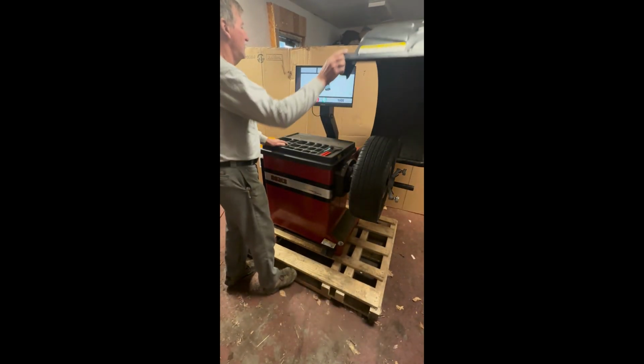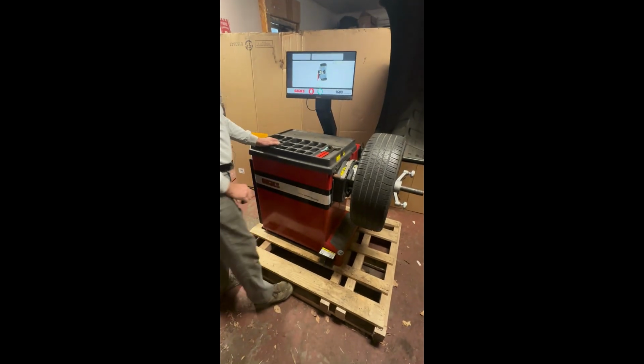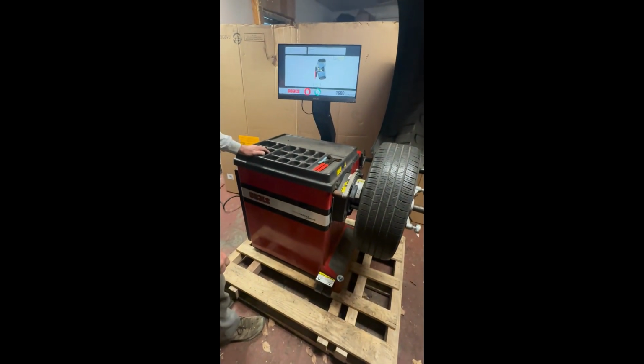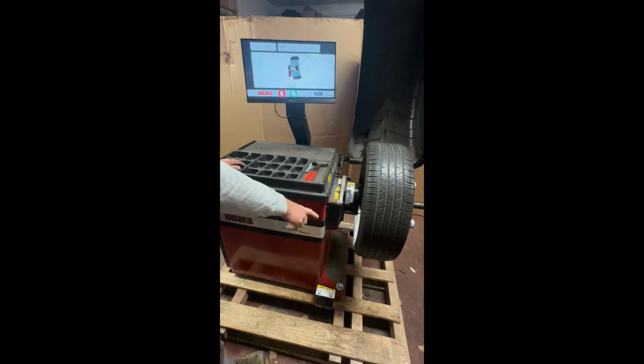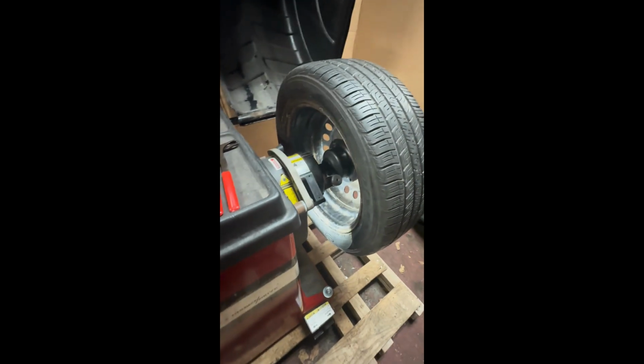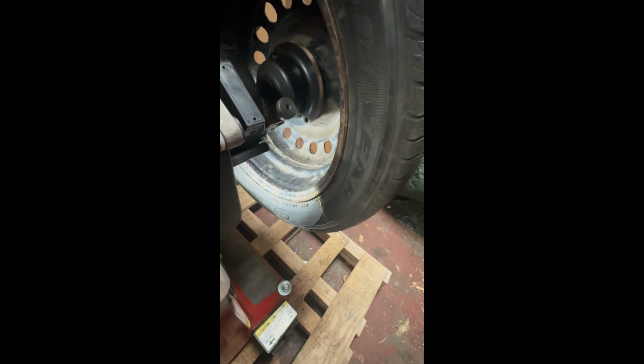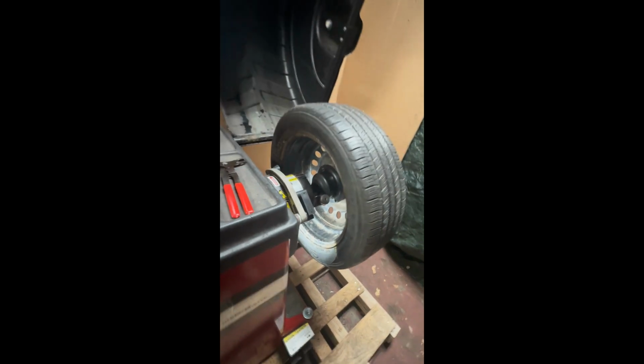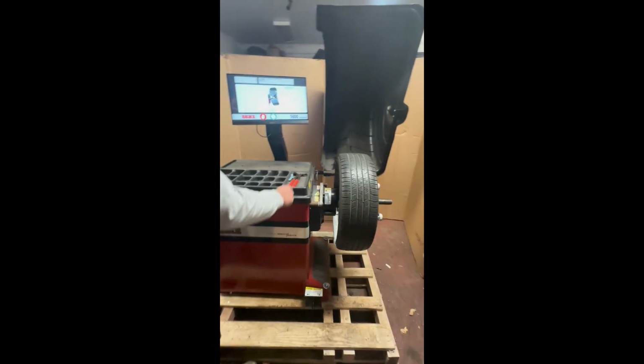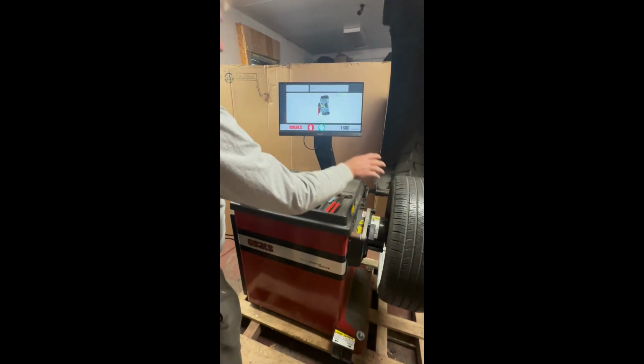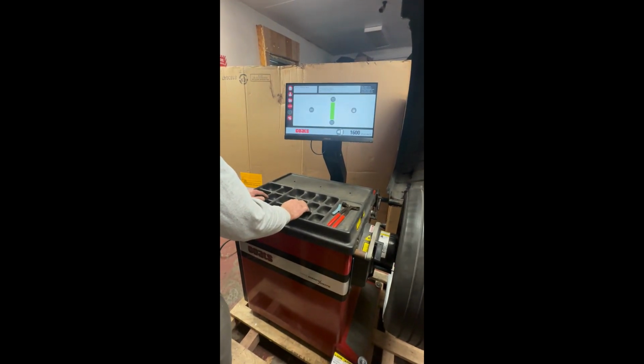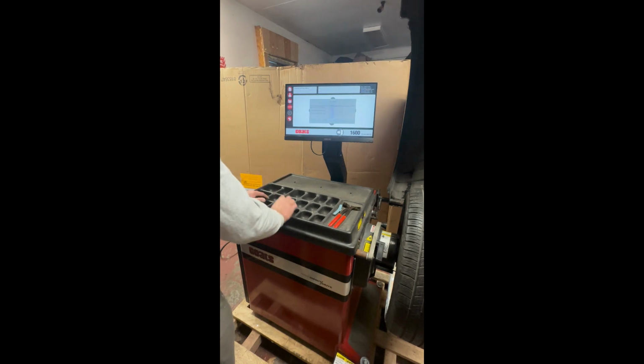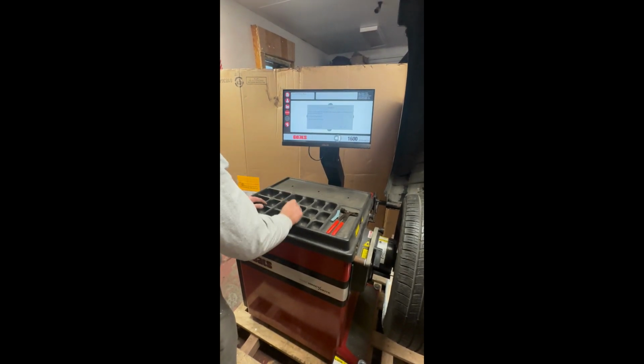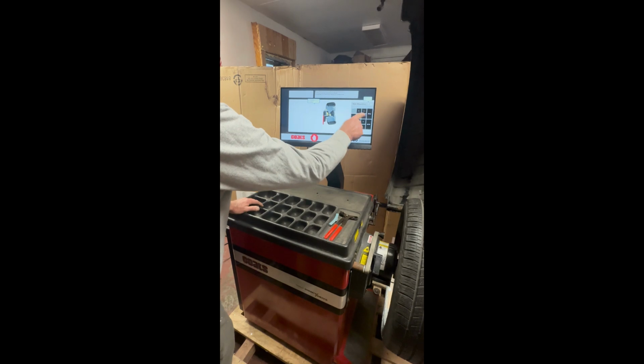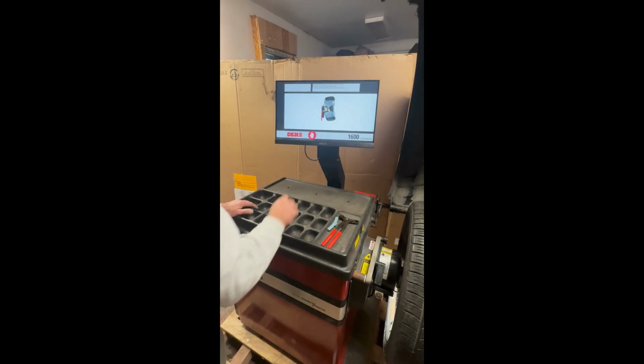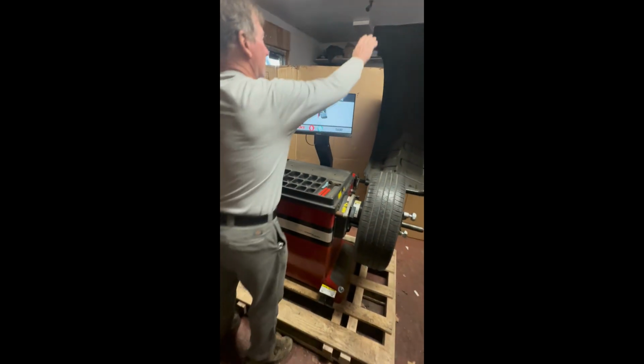So when it stops, we raise the hood, and we put the weight at 4 o'clock. However, on this particular time around, our yellow line, our 12 o'clock line, is at about 4 o'clock, and it's supposed to be at 12 o'clock. So I know that the balancer didn't stop in the right place. I'm going to discard this calibration by hitting stop, by hitting cal again, without doing anything. Hit proceed, put the 17 back in again, enter, lower hood, and touch spin.